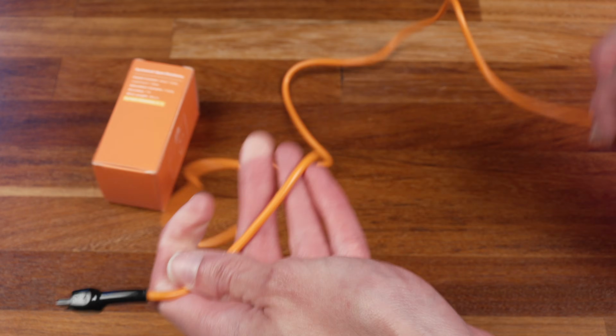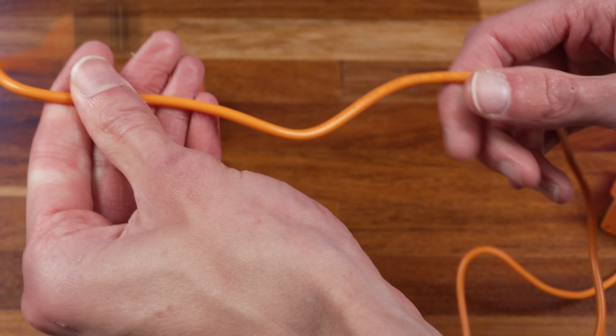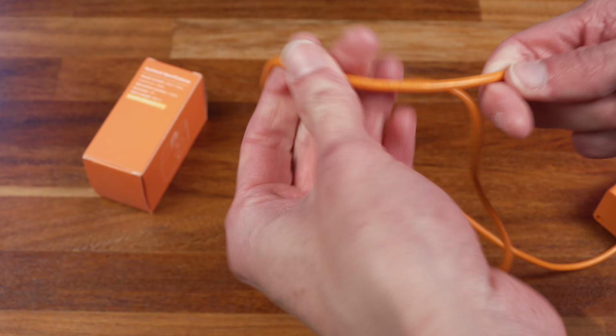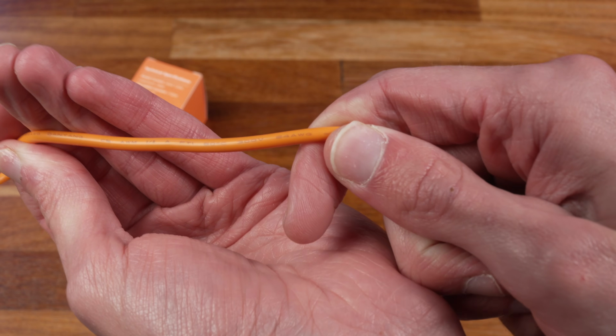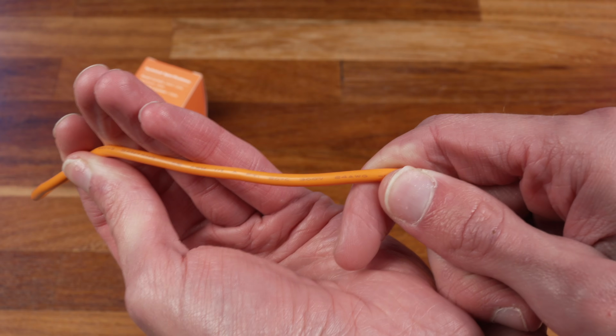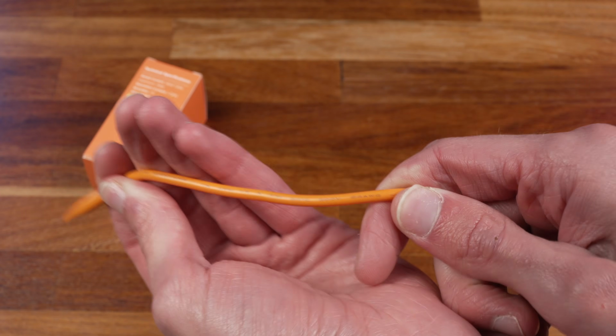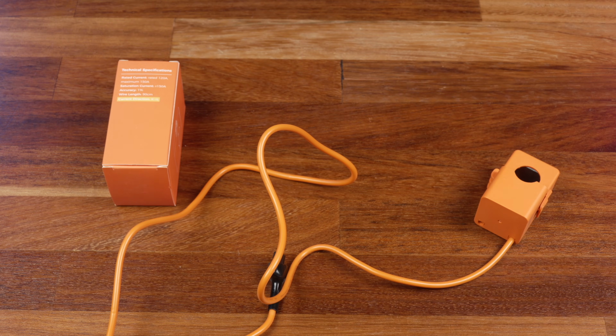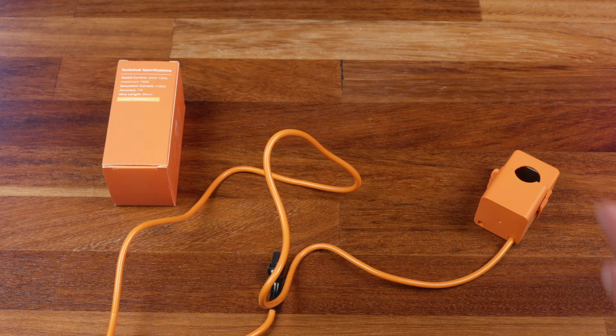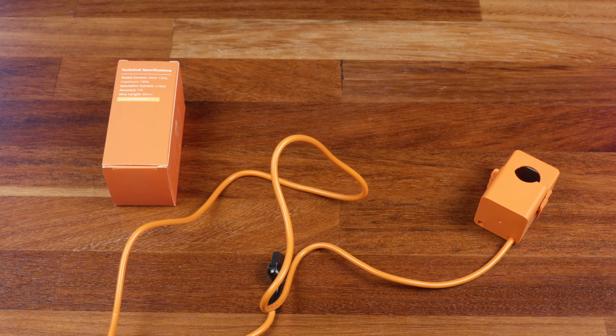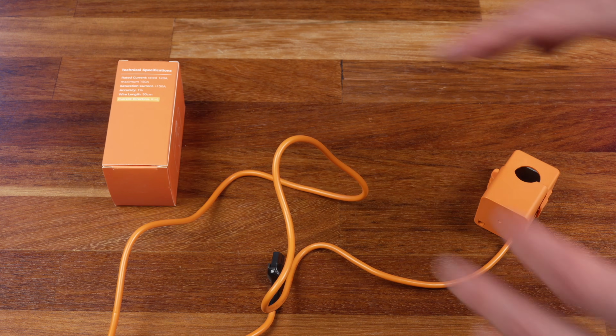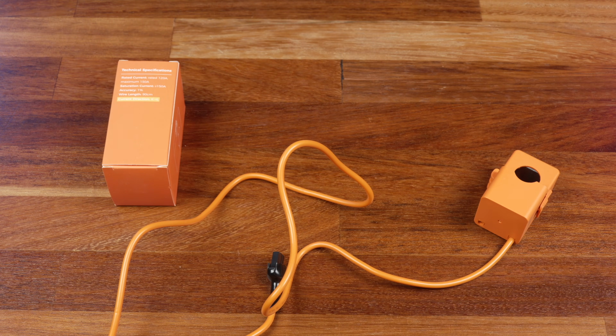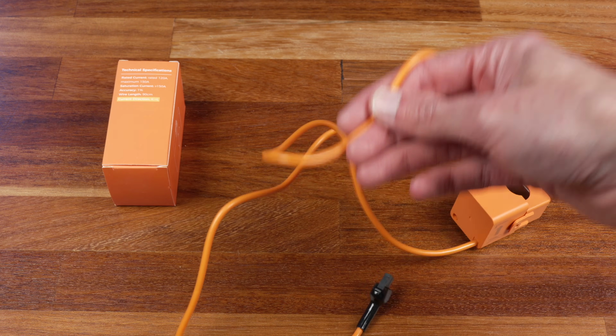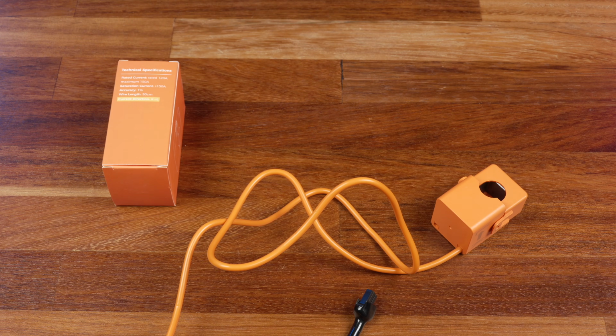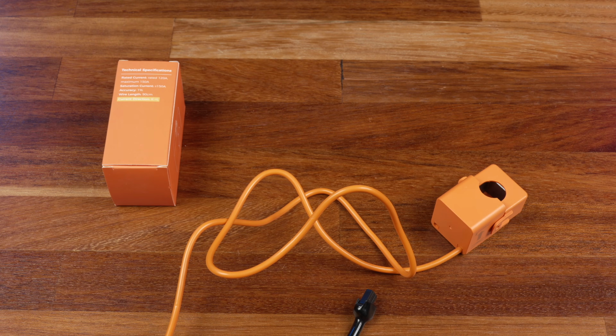That said though, what's really good here is that if you look at the cable and try and find it somewhere on the cable, we have the rating on it there. And you might be able to just about make out there that this cable is insulated to 300 volts. And this is important, since based on the UK's wiring regulations, if you're mixing band 1 and band 2, or mains voltage and lower voltage cables in the same enclosure, they should all be insulated to the highest voltage present. That means that since these CT cables are going to be installed in a consumer unit with mains voltages present, the cables need to be insulated to handle that mains voltage, which these are. Whereas some other CTs may come with wire that just isn't rated to such high voltage, so installing those in a consumer unit in the UK technically wouldn't be compliant.